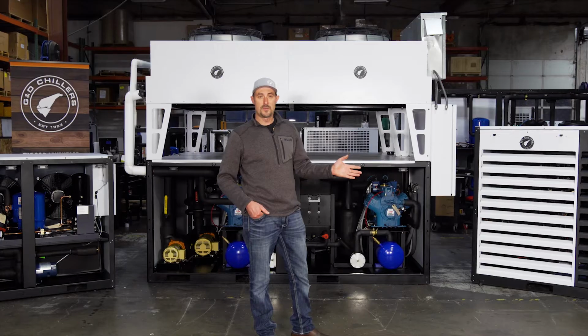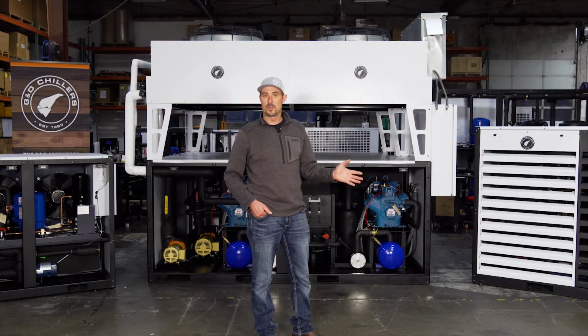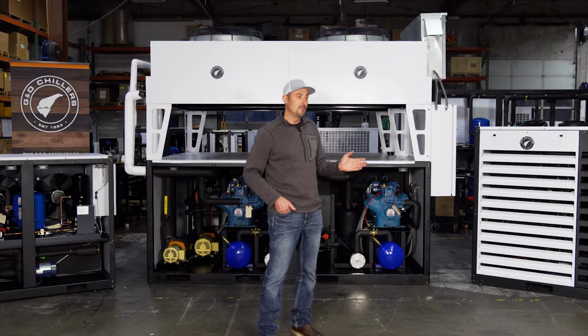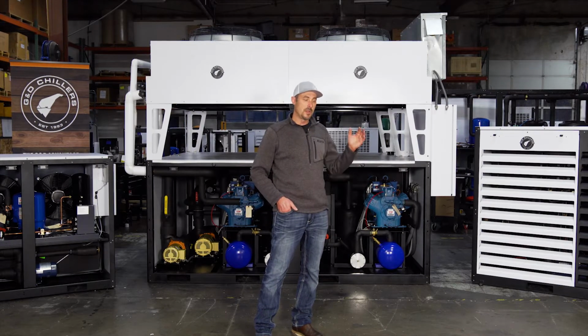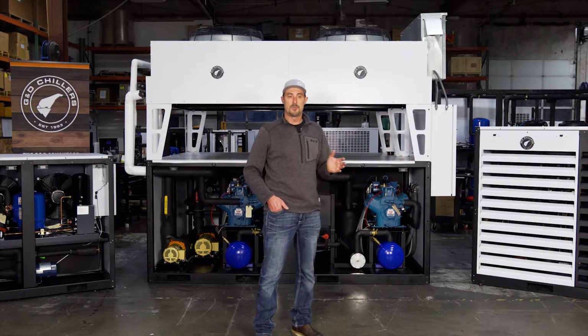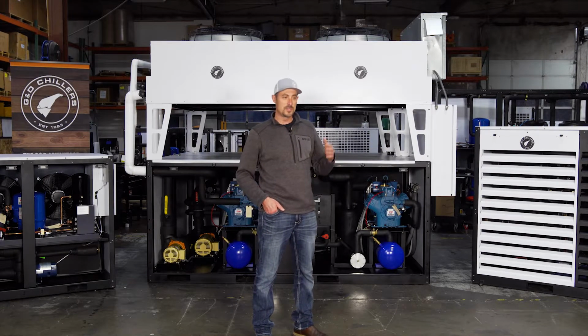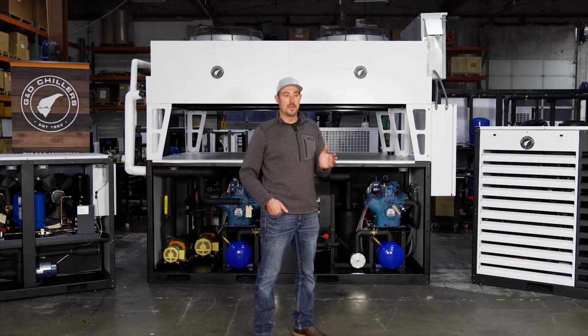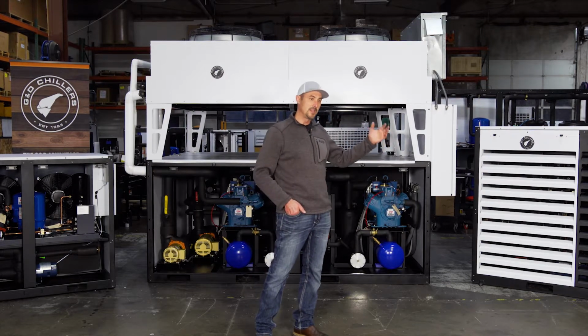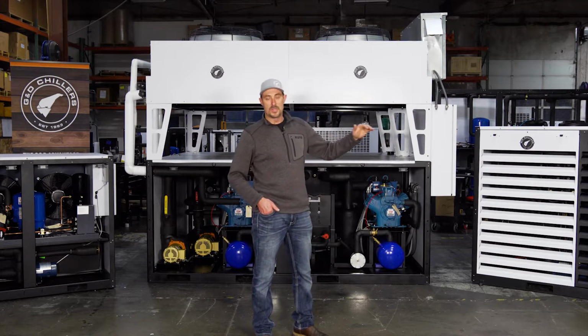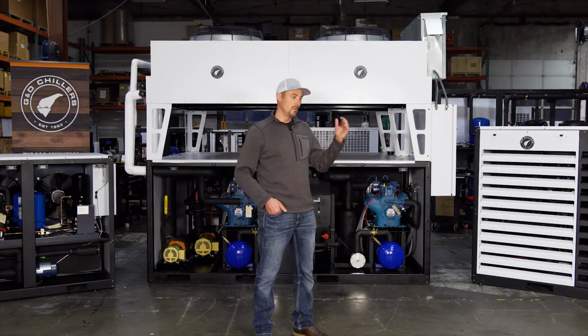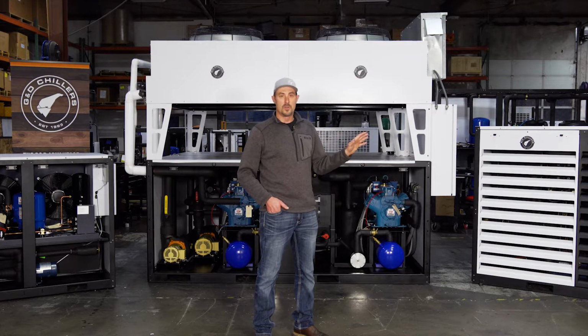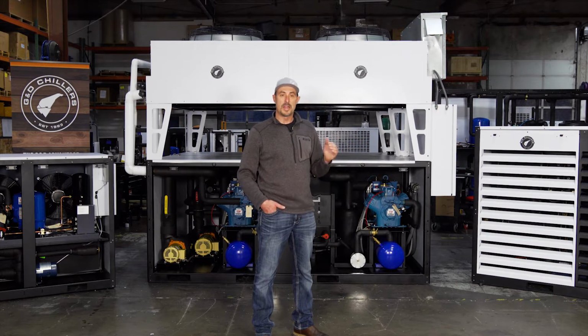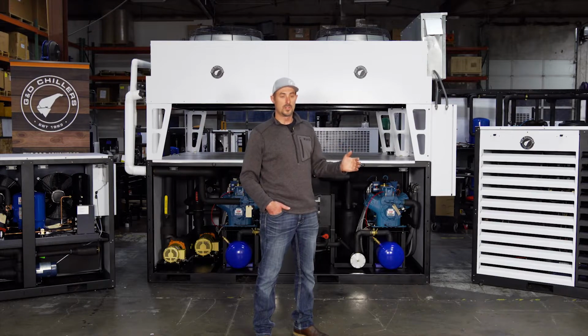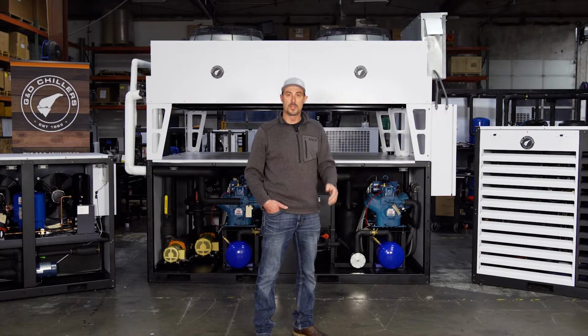One of the first questions everybody asks is, what size chiller do I need? We've been building chillers now for almost 30 years, and we've developed a fairly sophisticated program for sizing different tanks and different inlet and outlet temperatures. We can input the size of the tank or barrel, whether you're in active fermentation, crashing your tank, or knocking out your wort, and come up with an accurate BTU load to properly size which of these chillers would work best for you.